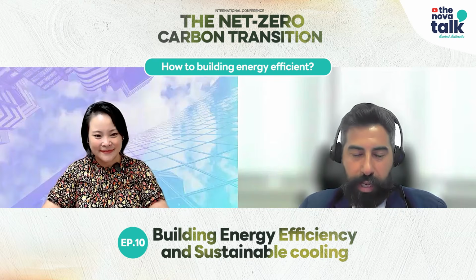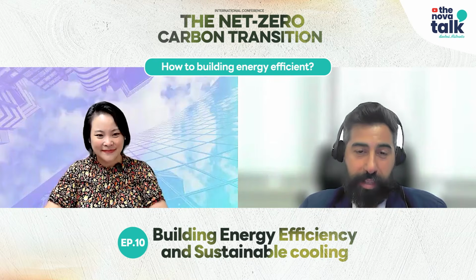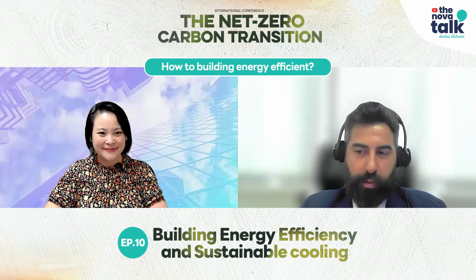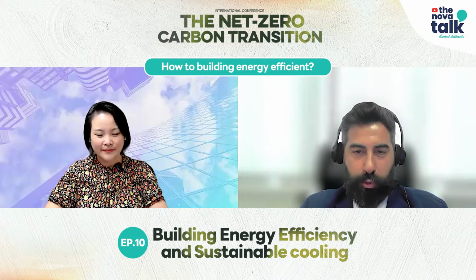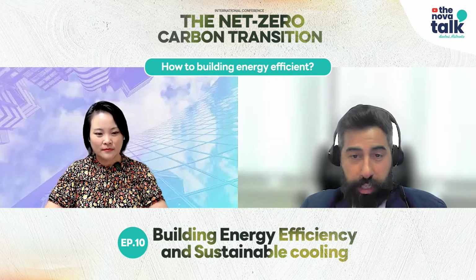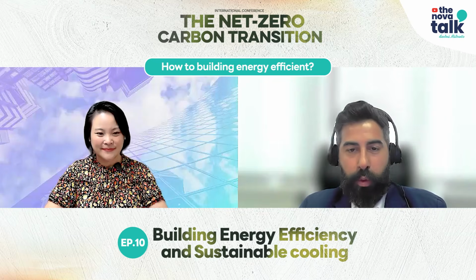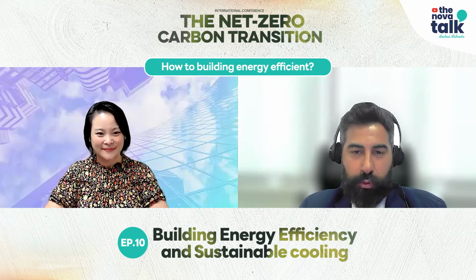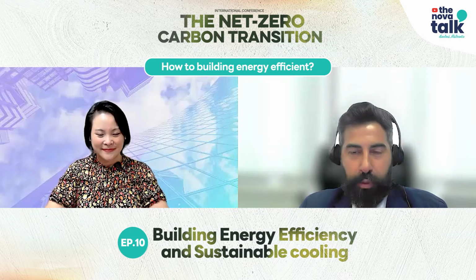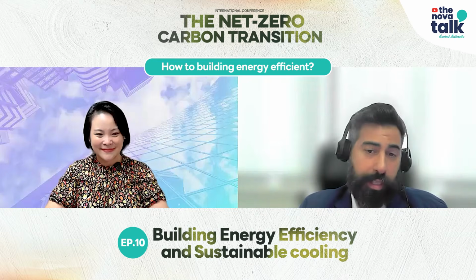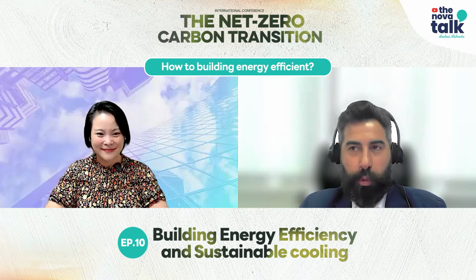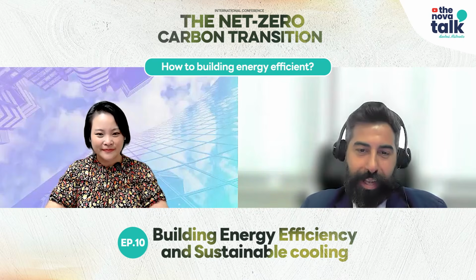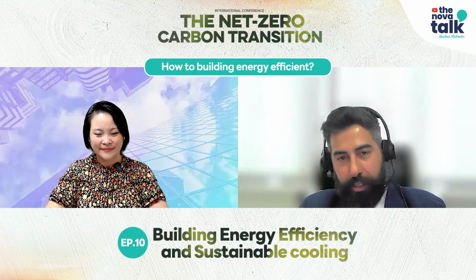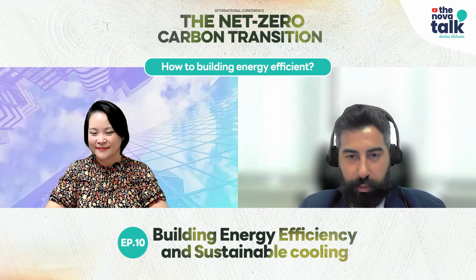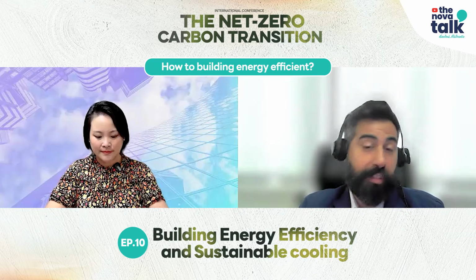Yeah, like you started with, passive design is the most important element. I think maybe you've covered that previously. So making sure the U values, the shading coefficient of the windows, the orientation, the window to wall ratio, all these are designed in a way to reduce the heat input from outside to the inside. So we're in Thailand, it's a hot and humid climate. So we want to keep the outside out and make sure we have a very strong barrier that reduces the heat transfer between the inside and the outside. So I think you've covered that topic before, and this is the most important part.